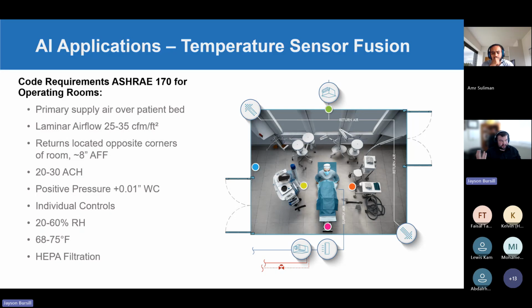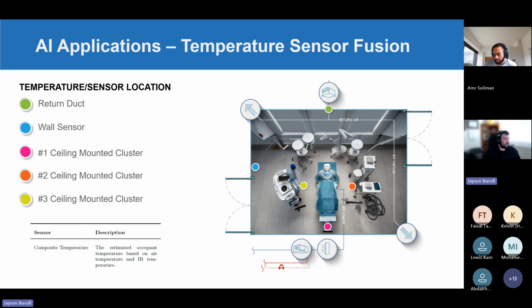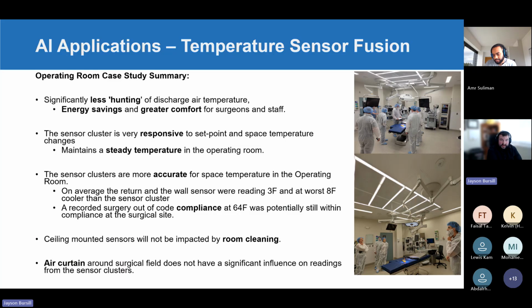So the idea is you could monitor temperatures inside the air curtain without actually having to be inside the air curtain that goes over the operating table. This was a case study using what we call a composite temperature, a combination of the air temperature on the ceiling and the infrared temperature that comes out in a cone from the ceiling-mounted sensor. There are some graphs, but the graph analysis takes a while, and I'm already running a bit behind here.